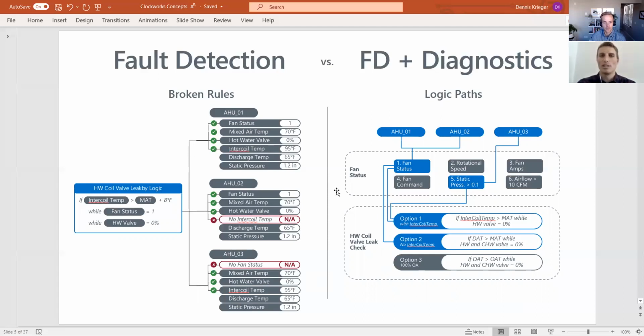It's hard to match these one-to-one, so we take a different approach: guiding each type of equipment, each controller configuration, through a set of logical paths to figure out what tells us when this thing is on, what points are available to determine airflows, delta T's, statuses, and how we can get to the same output—this hot water coil valve is leaking—regardless of whether we had 10 points on that air handling unit or 24 points or whatever it might be. We want to give you the highest quality output with the minimum amount of data inputs on each controller.